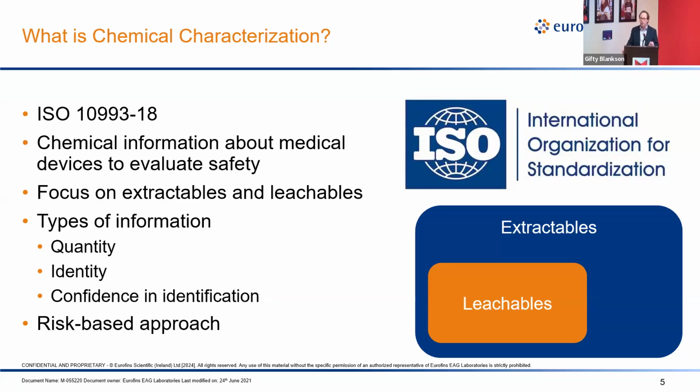There are things that could cause them. And we're doing that at pretty much the highest level that we can because we're looking at medical devices. Part 18 focuses on extractables and leachables. So this is not about if I take the whole device and put it on something or someone, is it going to be a problem? It's looking at what leaches or extracts out of it, right? In common English, extractables and leachables are synonyms, but in this field, they're technically different.